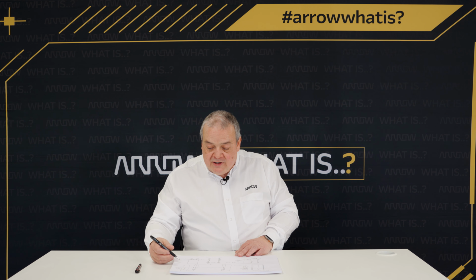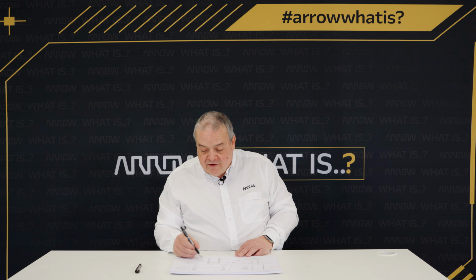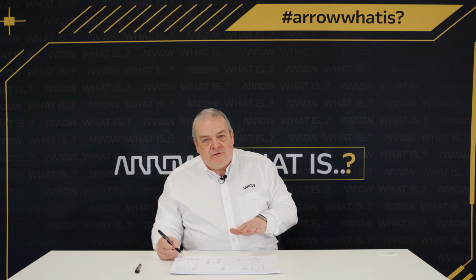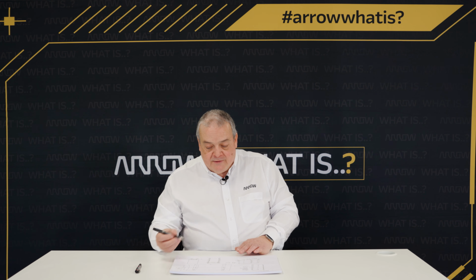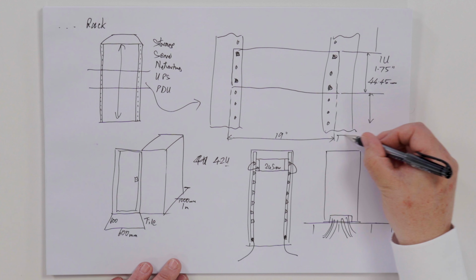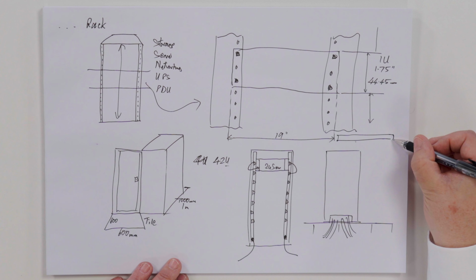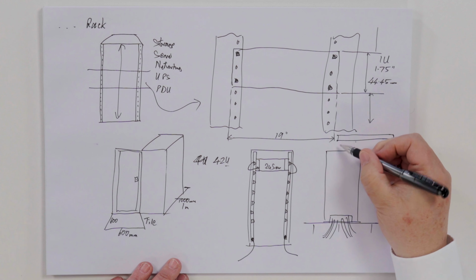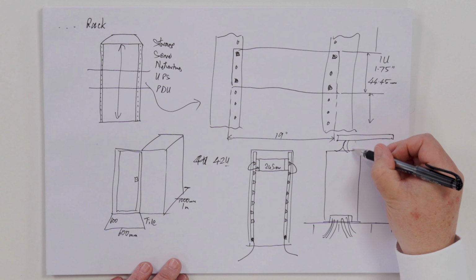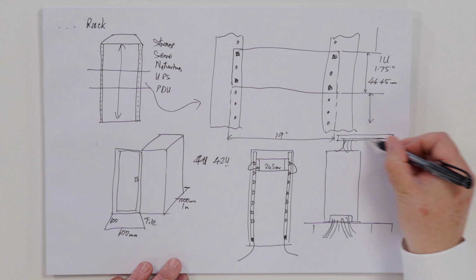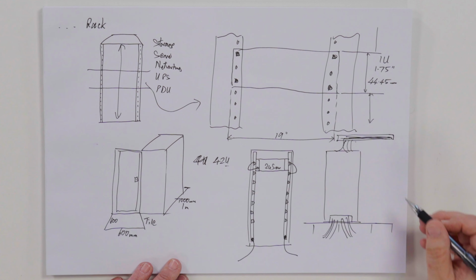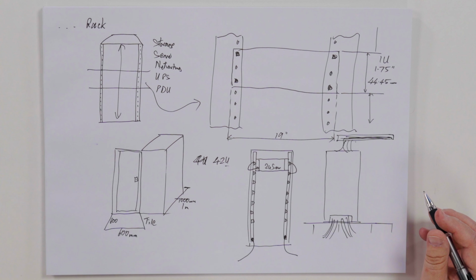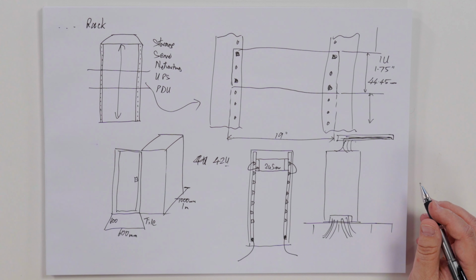There are some companies that don't have a raised floor, and the rack sits straight on the concrete slab of the data center. So there's no way to go down - so what you do is go up. You put cable trays in the upper part of the computer room, and when the cables come out of the top of the rack, they sit inside the tray and move across to other racks or other technology elsewhere in the computer room.